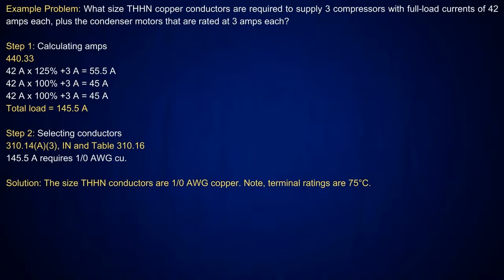Now, this one, like I said, you take the largest motor at 125%. Everything else is added at 100%. Okay, so let's take a look here. I've got 3 compressors. They're all the same, 45 amps or 42 amps each, and each condenser is rated at 3 amps. So you'll see in 440.33, I took one of the 42 amps at 125%. Everything else was added at 100%. See that? So add all of that up, it gives you 145.5 amps.